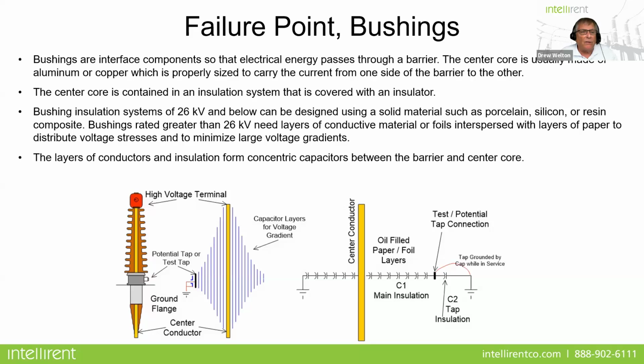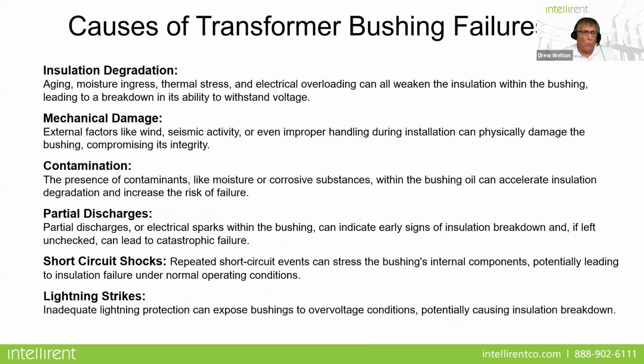And we know that bushing insulation systems of 26 kV and below are designed using solid materials such as porcelain, silicone, or resin composite. But bushings rated greater than 26 kV need layers of conductive materials, as we see here in the diagram. Conductive materials or foils interspersed with layers of paper to distribute voltage stresses and to minimize large voltage gradients. These layers of conductors and insulation form concentric capacitors between the barrier and the center core.